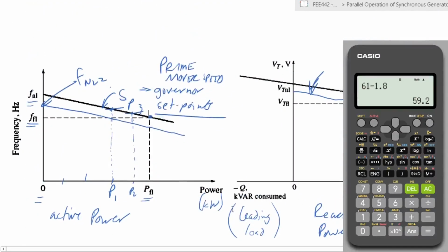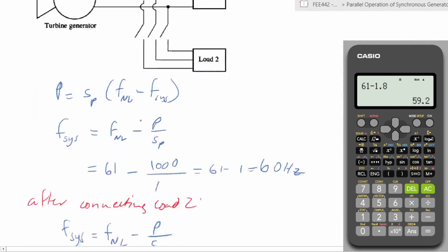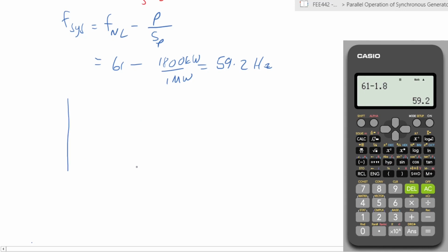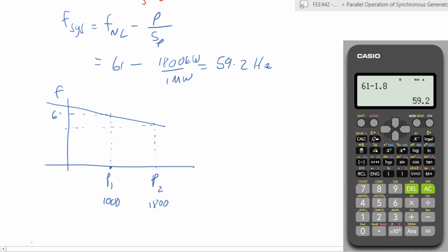So what would we need to do? Here what we are talking about is what we had discussed on this point. We want to run this generator at this set point, okay? So if we look at it diagrammatically, you have your set points looking like that. So you had your P1, which is 1000 here. Then you had P2, which is 1800 at that frequency, right? So this is frequency 1, this is frequency 2. Frequency 1 is 60, frequency 2 is 59.2. Okay, this is at no load, this is 0. So what do you need to do in order to get the machine to supply 1800 kilowatts, but at a frequency of 60?